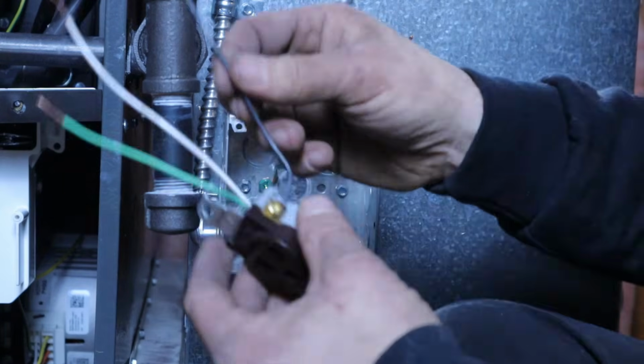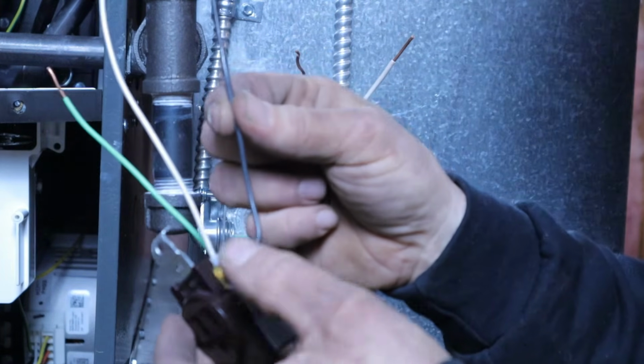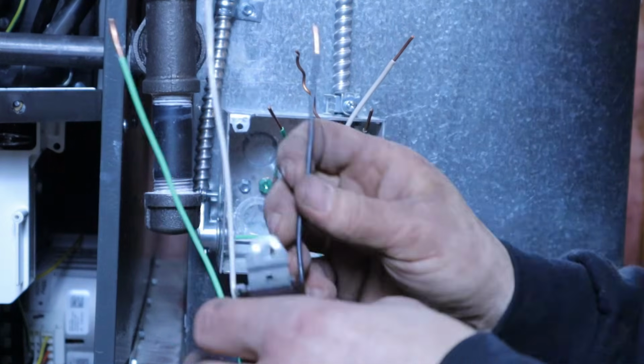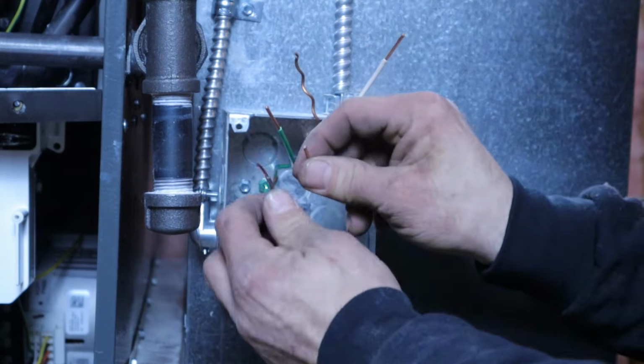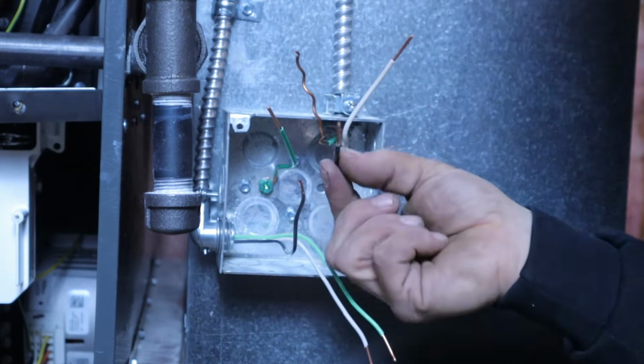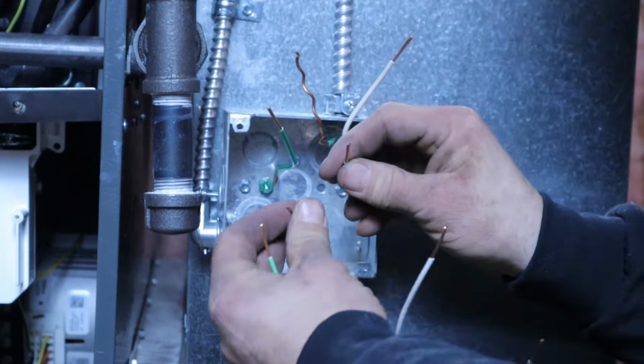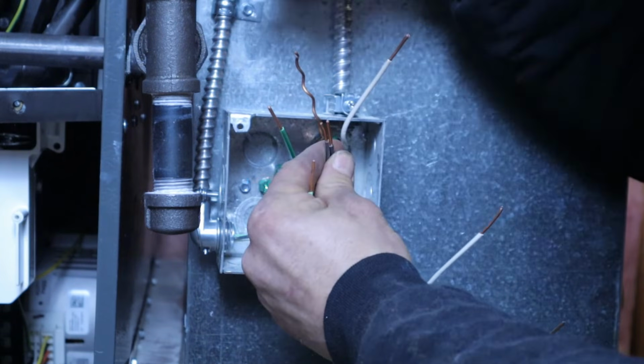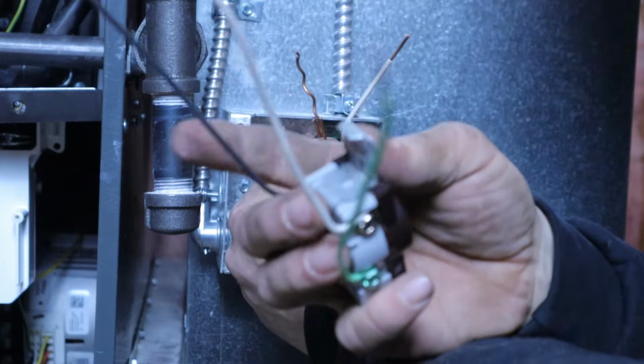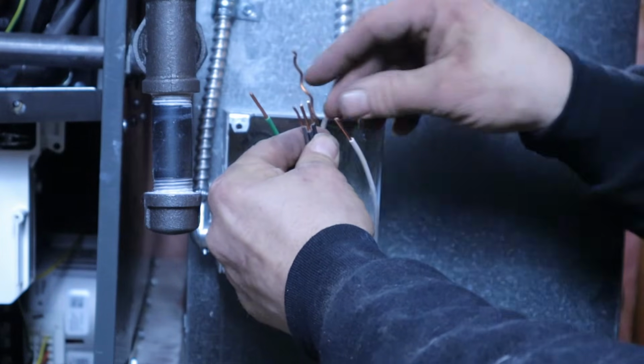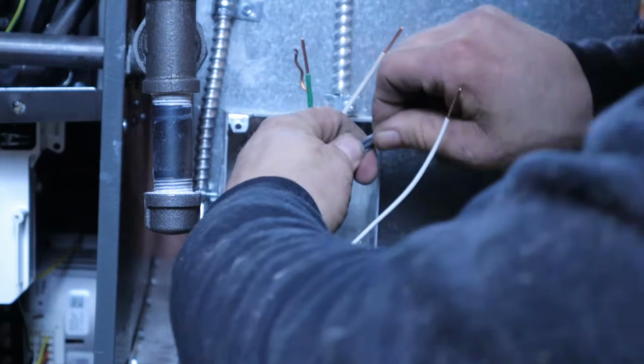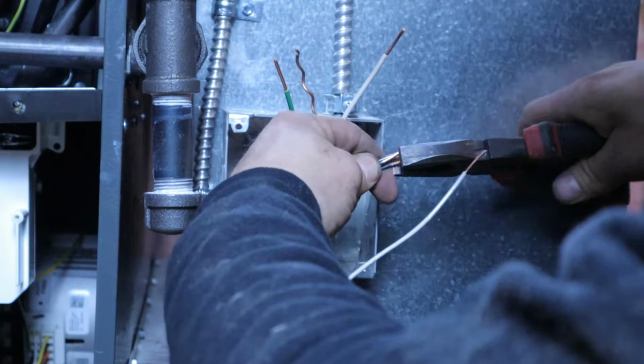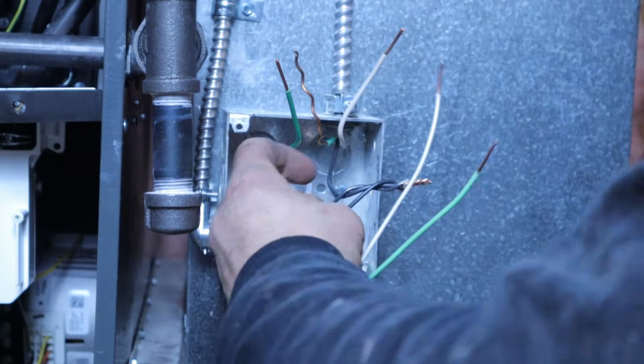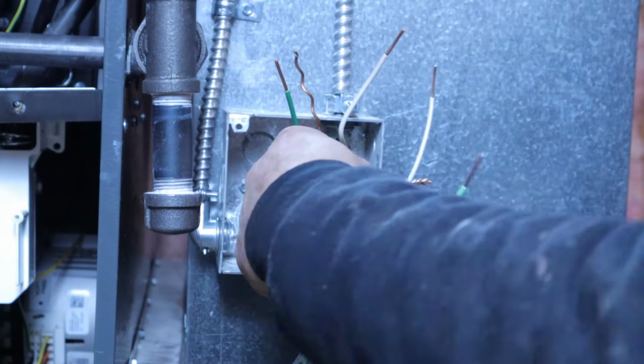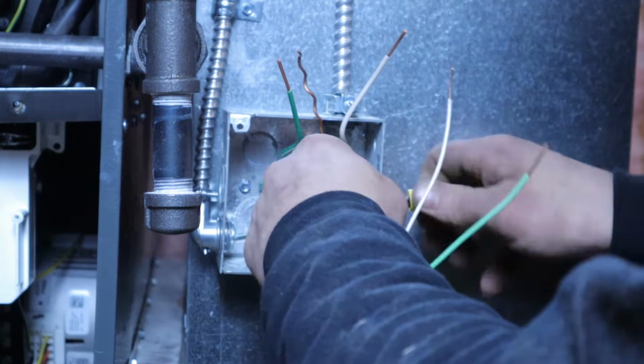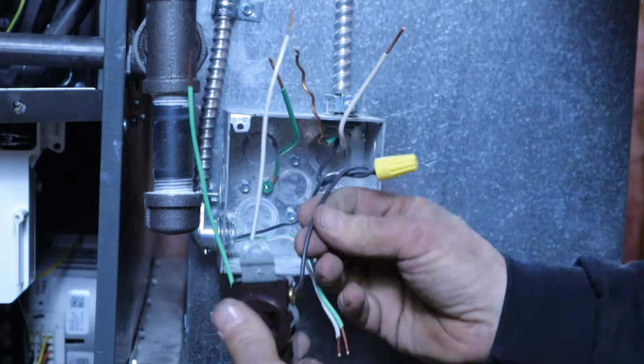So what I'm going to do is take this black wire, that's the load for the outlet, and tie that right into all the other blacks here. Our power is going to be coming in on this black wire. It's going to go right to the black wire that feeds into our furnace, but it's also going to come off and go to the black wire for our outlet. So I'll tie those three together. Put a wire nut on there. And so there we have our path.